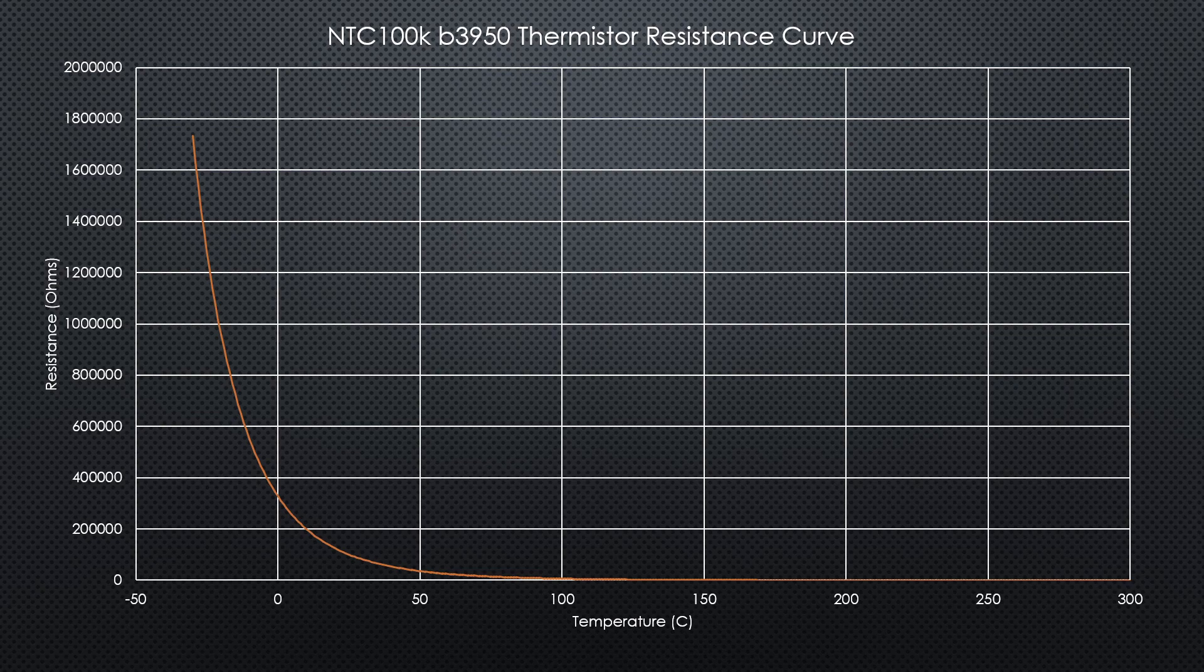The second part I want you to note is that this curve is really not linear at all. So if you pick two points on this curve, draw a straight line between them, and try to estimate the temperature versus resistance response, you're not going to match this curve at all. It also comes into effect later on as we're looking at the ADC resolution and some other things like that for accuracy. But that will be touched on more in the next video.